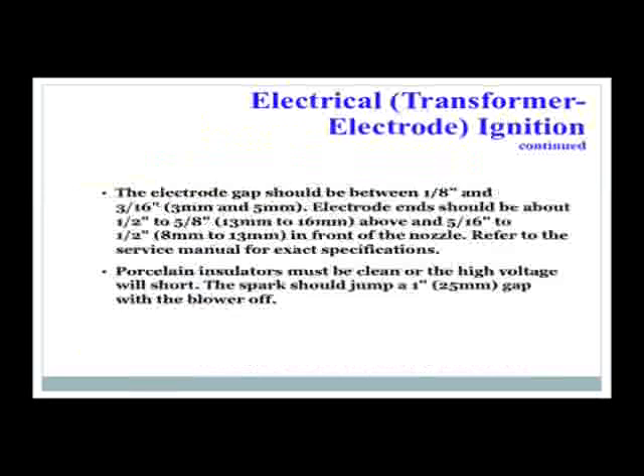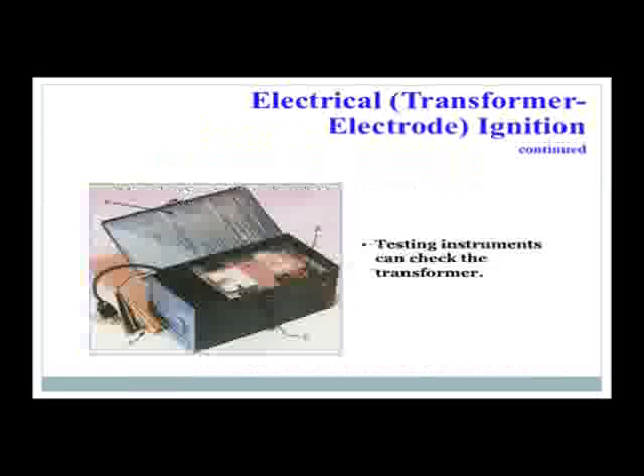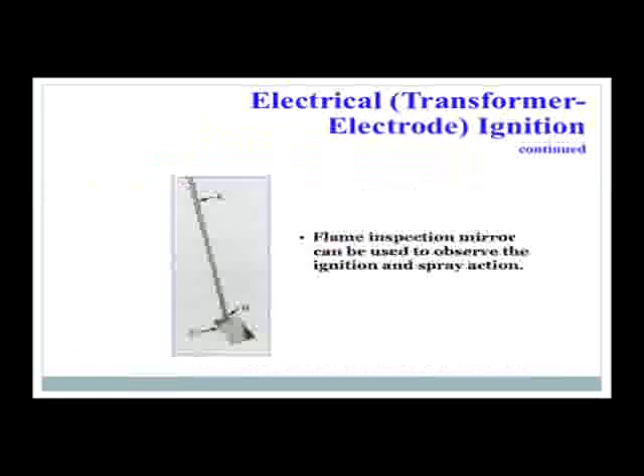The electrode gap should be between 1/8 of an inch and 3/16 of an inch. Electrode ends should be between 1/2 an inch and 5/8 inch above and 5/16 to 1/2 an inch in front of the nozzle. Again, the service manual for the specific burner will give you the exact specifications. Porcelain insulators must be clean or the high voltage will short. The spark should jump at a 1-inch gap with the blower off. You can use testing instruments to check the transformer, and a flame inspection mirror can be used to observe the ignition and the spray action. Make sure the inspection mirror is made of metal and not of plastic.